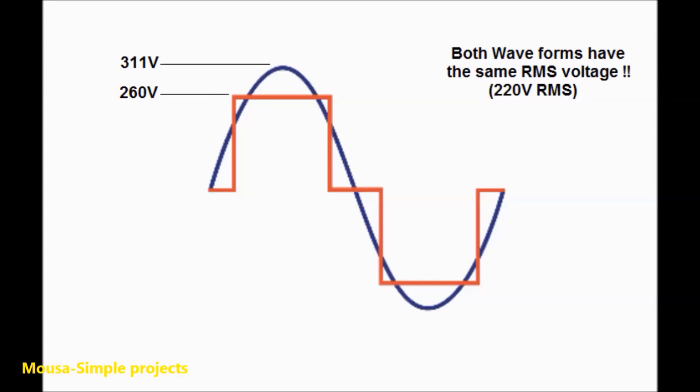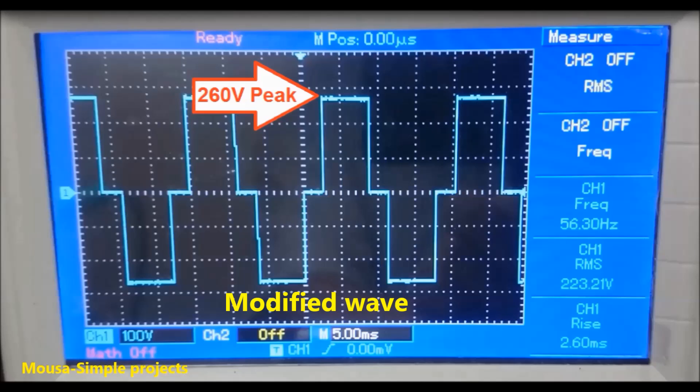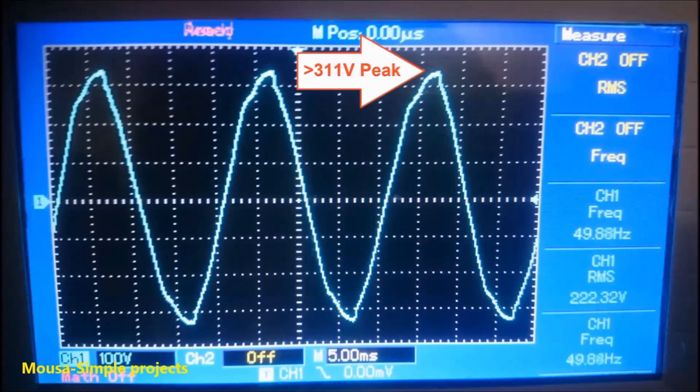The square wave peak voltage should be 260 volt to give us 220 volt RMS, but the sine wave peak voltage should be 311 volts to give us 220 volt RMS.